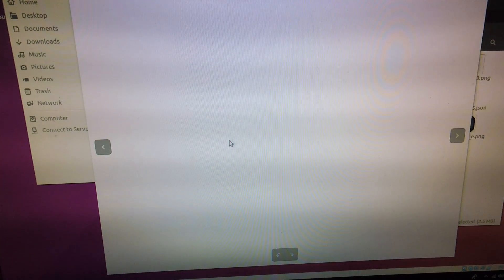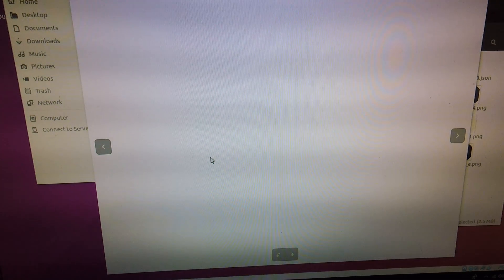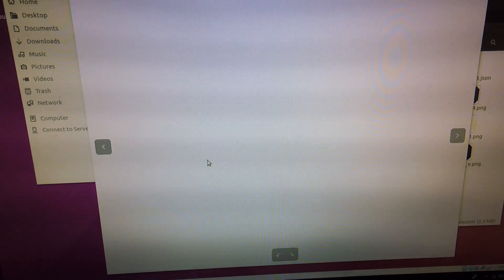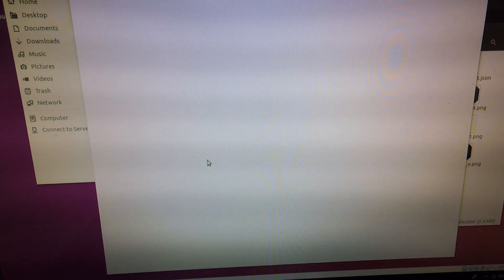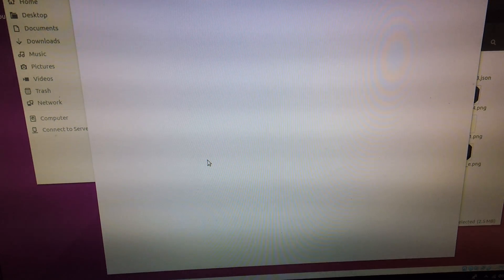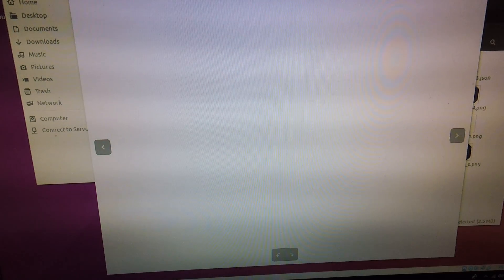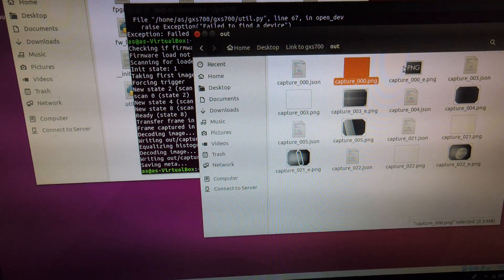So if we look at that that's just pure white. The dental x-ray sensors in contrast to the scientific x-ray sensors have the color scales inverted to simulate dental x-ray film. So on actual dental film the white would be a lack of x-ray exposure and black when the film darkens would be x-ray exposure. So the colors are inverted.